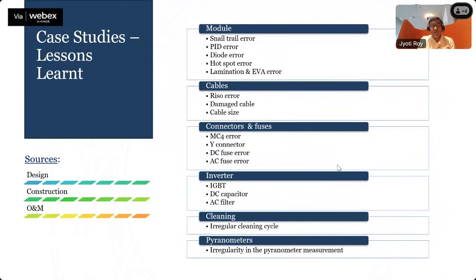There was a 50% undersized cable installed. So when irradiance was higher, the system produced more power, but because of the current-limiting capacity of those cables, they weren't able to export it all.